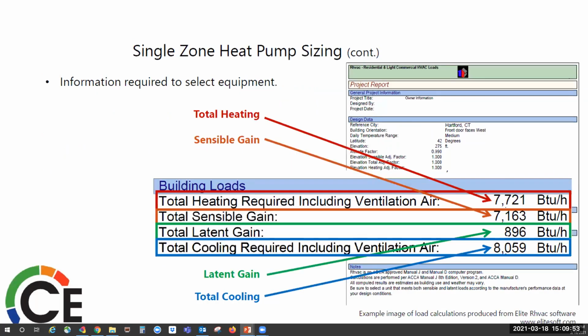For this example, we have a 7,721 BTU heat system and a total cooling of 8,059. Now remember, these are variable speed units. For multi-head systems, you'll also need to do a load calculation for each room. I had a few rooms large enough that they have two separate heads in there. If it's a large enough room and you need 2 tons of cooling in there, you're going to think about putting 2 different heads in there, depending on how large it is.